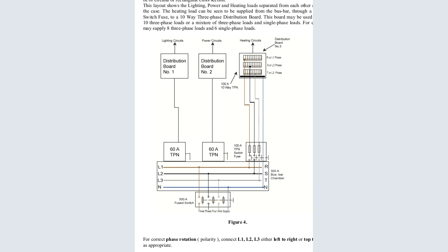This is the isolator for distribution board number 1, the isolator for distribution board number 2, and the isolator for distribution board number 3. And you remember that these isolators are still taking the 3 phases. At this point, all the distribution boards are still tapping the 3 phases. And now you can distribute and say, let this phase go to the lighting circuits. These are normally for storage buildings, where you can subdivide the building so that one phase goes to this building and the other phase to the other building, and then there is the power circuit and the heating circuits are here.